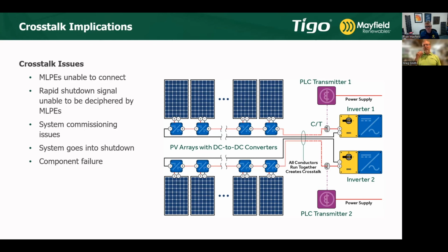So, if you're, and we get this call all the time, hey, I just commissioned this system and I'm getting like no voltage at the inverter. It's like, well, what is the voltage? Can you divide that by 0.6? And does that number equal the number of modules up on the roof? Oh wow, yeah it does. How did you know? Oh okay, well your RSS transmitter doesn't have any power. Yeah, interesting. I wish they were all like that. Right, exactly.